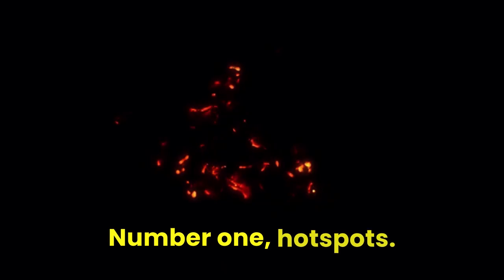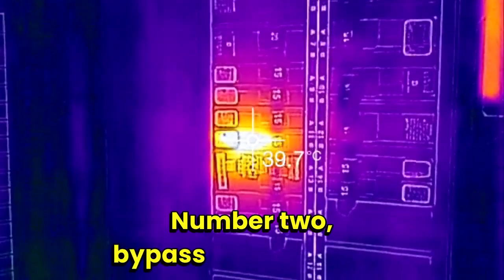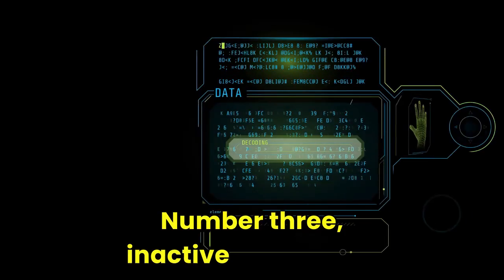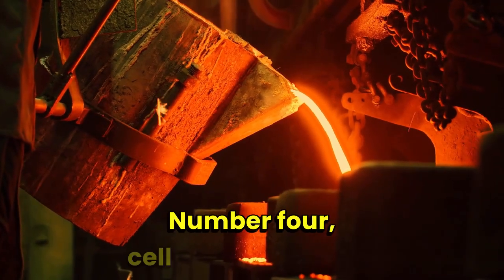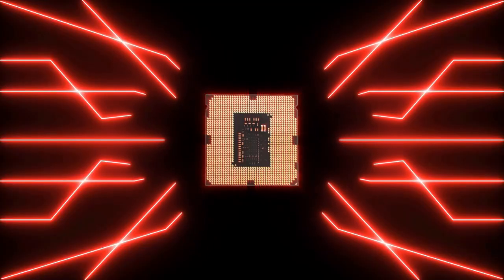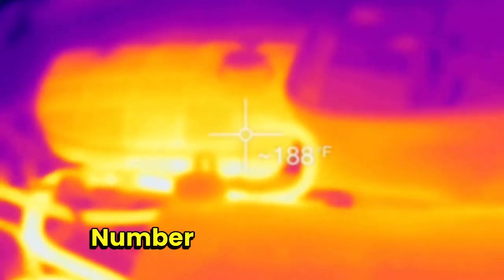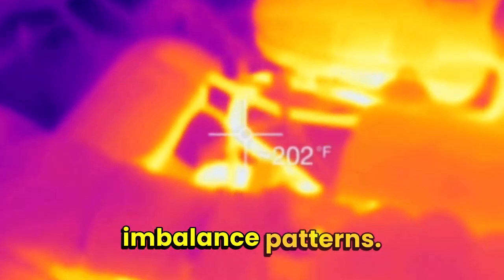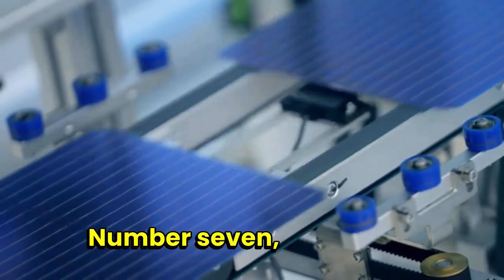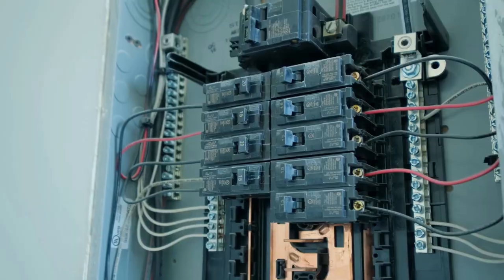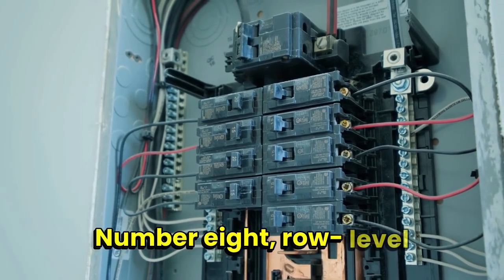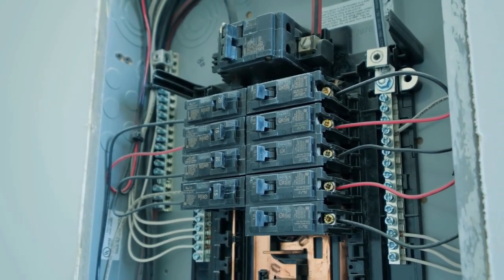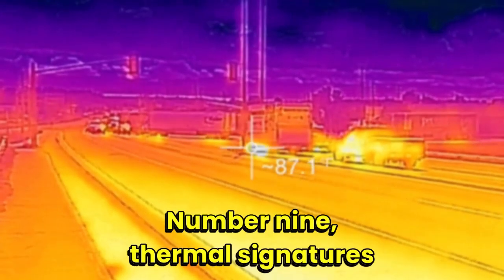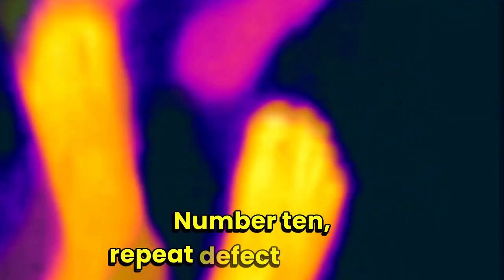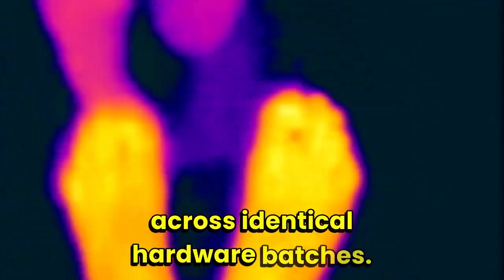Number 1, hotspots. Number 2, bypass diode failures. Number 3, inactive substrings. Number 4, cell cracks creating abnormal heat signatures. Number 5, connector heating. Number 6, fuse-related imbalance patterns. Number 7, mismatch across neighboring modules. Number 8, row-level underperformance clusters. Number 9, thermal signatures linked to tracker behavior. Number 10, repeat defect patterns across identical hardware batches.